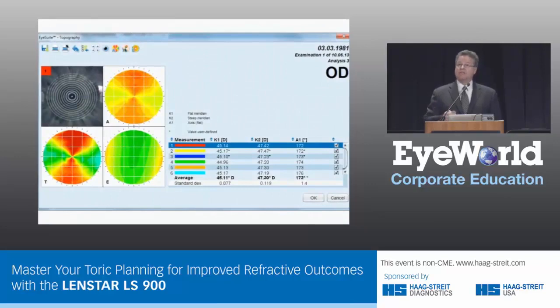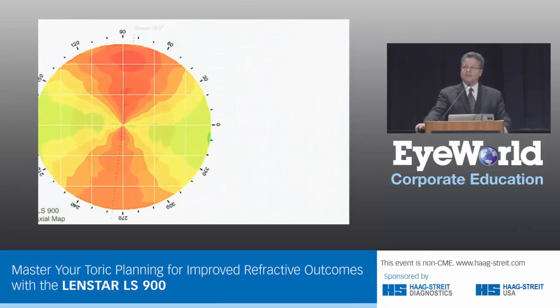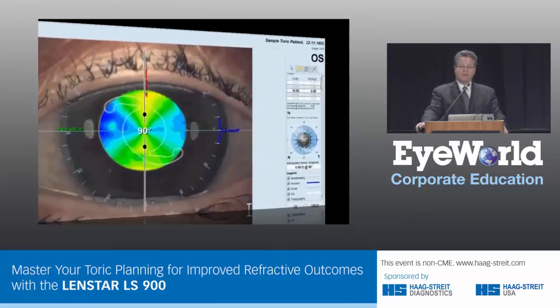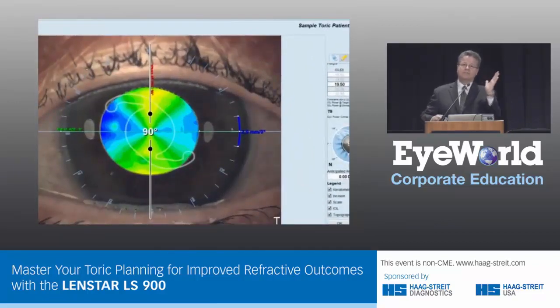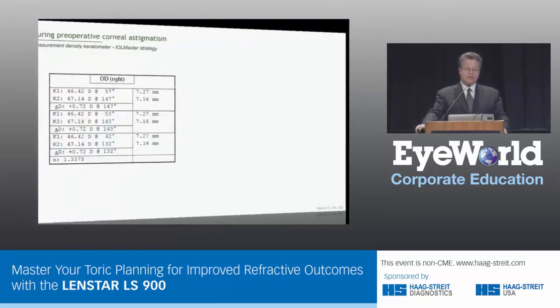So the T-cone can be used with confidence in place of the regular Ks on the LENSTAR, and it also gives us an axial topographic map. You can see it's not very intrusive — it sits right in front of the patient's eye. With a single button push, you get the topographic map, your Ks, and all the axial measurements. You don't only get that — you get several other types of topographic maps. If we just look at the axial map and click on it, there's what it looks like expanded, and here's what we use for determining the steep and flat meridians and the keratometry values for the power difference. This is pretty much all-in-one: everything you need for that part of the Toric IOL. Also on the LENSTAR is a line you can move left and right to superimpose the topographic map on the image of the eye, line everything up, and read the steep meridian with this all-in-one device.